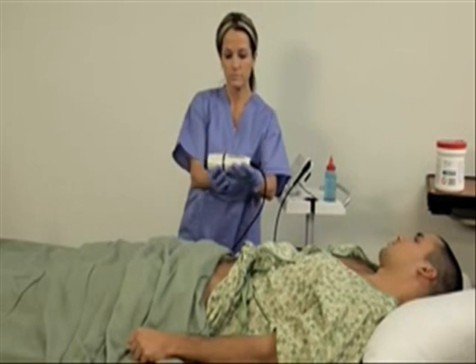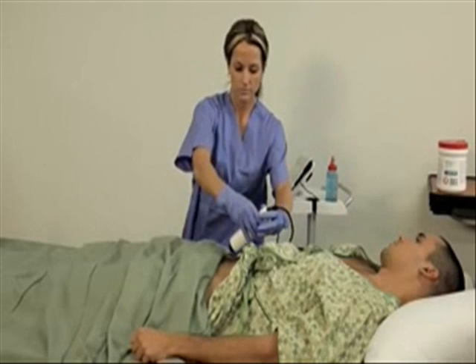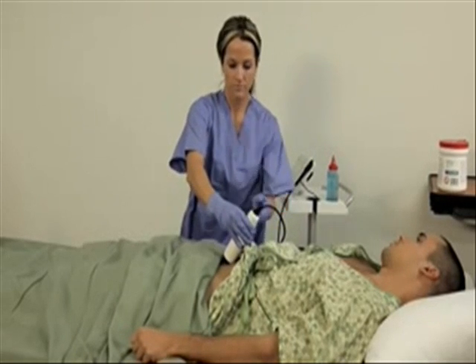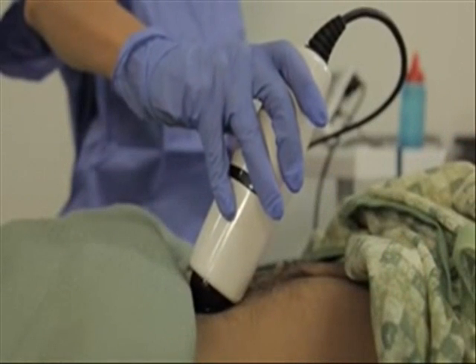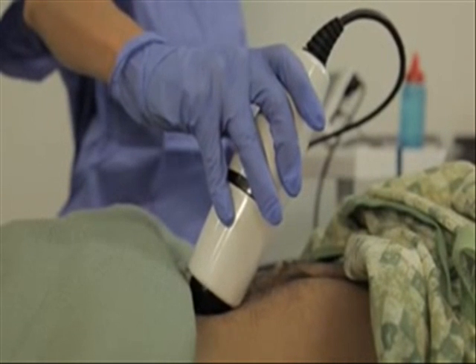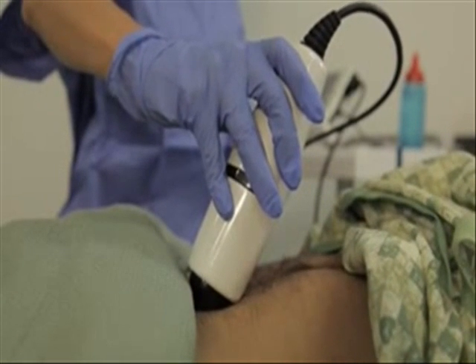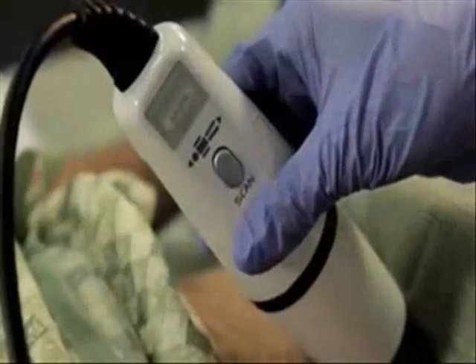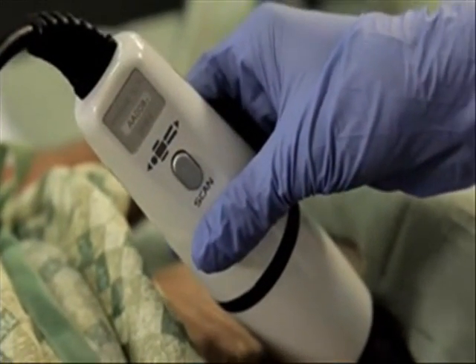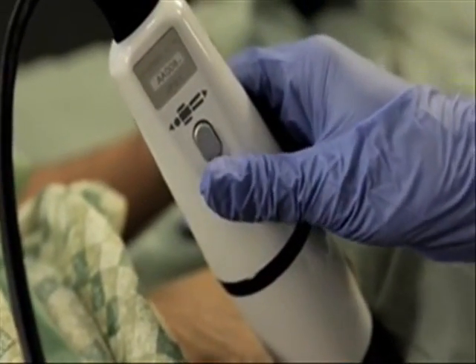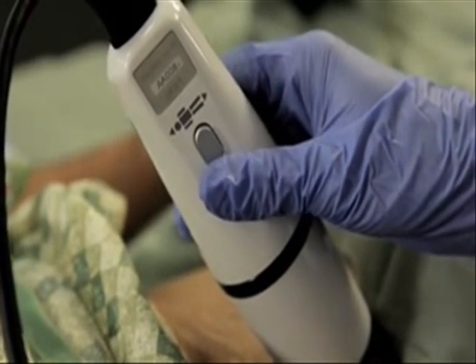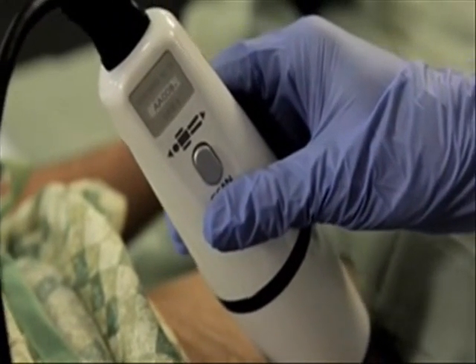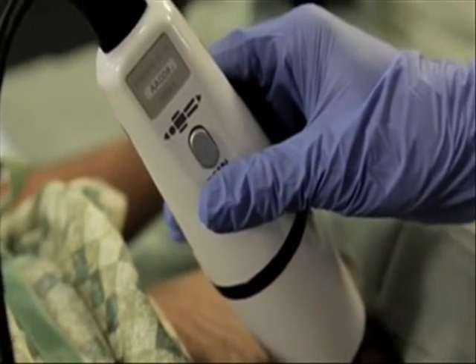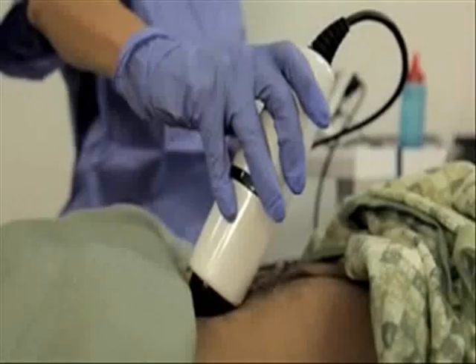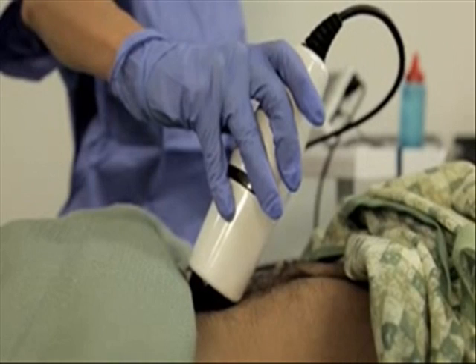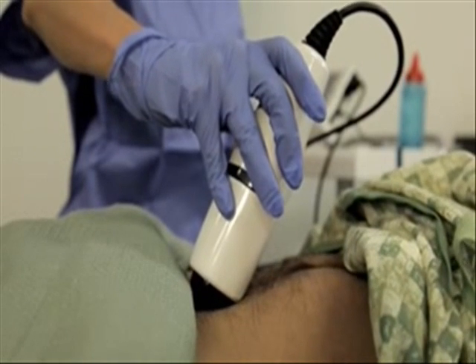The Biocon 700 has a unique feature that lets you see a live picture of what you're about to scan. We call this the pre-scan function. It takes the guesswork out of positioning the bladder scanner and greatly improves accuracy. To begin the pre-scan, press the scan button on either the touchscreen or the probe itself. If you are pressing the scan button on the probe, you do not need to hold the button down to perform the scan. Place the probe a few inches below the navel at a 60-degree angle from the patient.